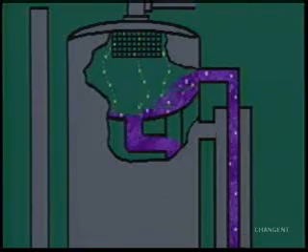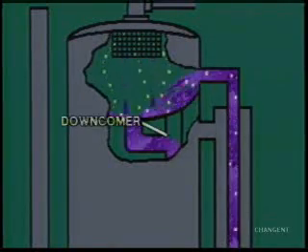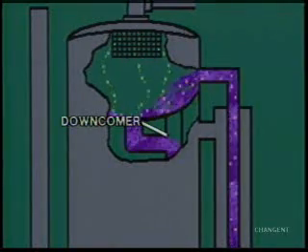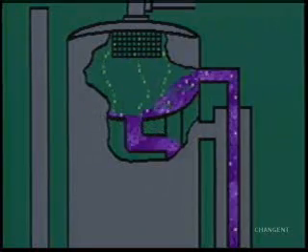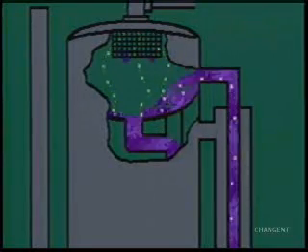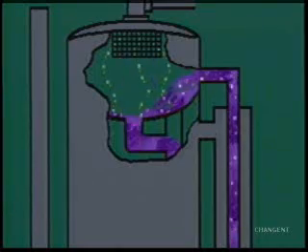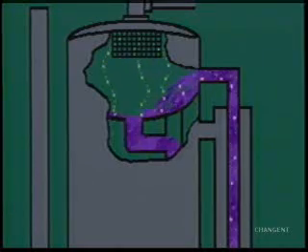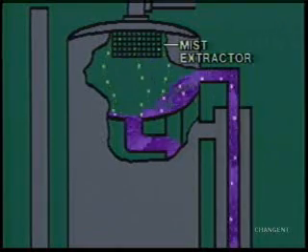Preheated emulsion enters the vessel, splashes over a pan, and flows into the downcomer. On its way down, the emulsion releases free gas due to the agitation created as it strikes the diverter plate. The gas leaves the treater through a mist extractor at the top of the vessel.